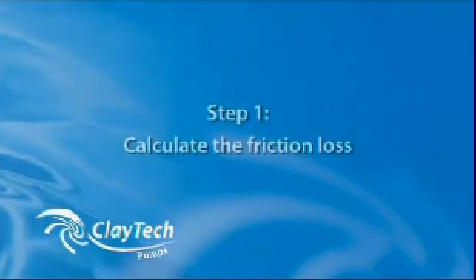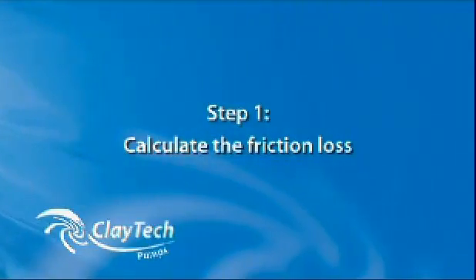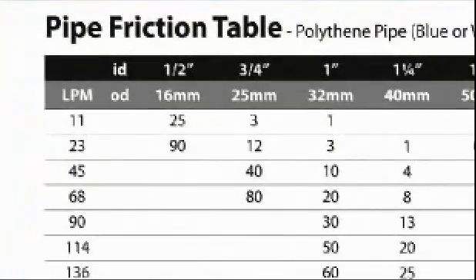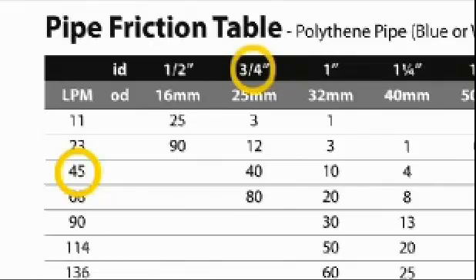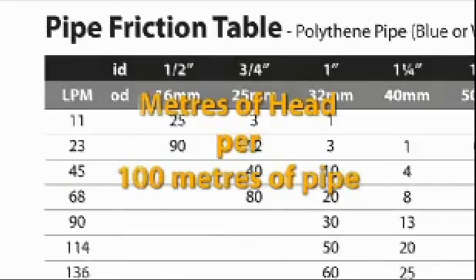The first step is to calculate friction loss. Remember, friction loss can be calculated using a pipe friction table. At 45 litres per minute and using a pipe 3 quarter inch inside diameter, we can see that there will be 40 metres of pressure lost to friction. However, in this chart, all values apply to 100 metres of pipe.